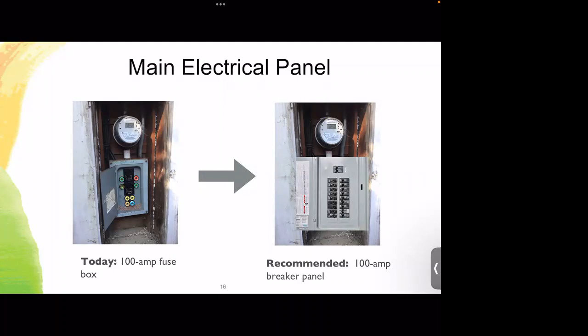This, from an electrical perspective, it's sufficient. From a practical perspective, we wanted to run new circuits into this box, and you can't drill new holes for those fuses or put new fuses in. So we decided to recommend that they swap out that old 100 amp fuse box for a 100 amp breaker panel. So same amount of electricity flowing through it. PG&E doesn't need to be involved, but they get a new breaker panel instead of this old fuse box. So from a safety perspective, it's probably better. The old fuse box has been serving them well, and there's been no issue, but it doesn't hurt to replace these.